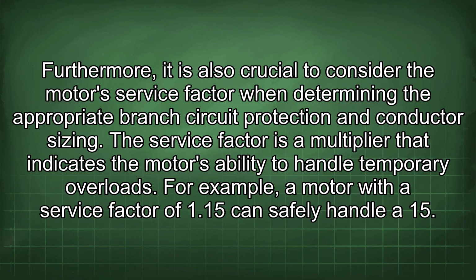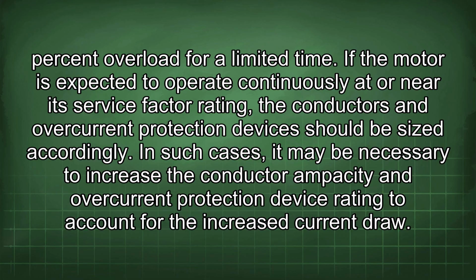Furthermore, it is also crucial to consider the motor's service factor when determining the appropriate branch circuit protection and conductor sizing. The service factor is a multiplier that indicates the motor's ability to handle temporary overloads. For example, a motor with a service factor of 1.15 can safely handle a 15% overload for a limited time. If the motor is expected to operate continuously at or near its service factor rating, the conductors and overcurrent protection devices should be sized accordingly.